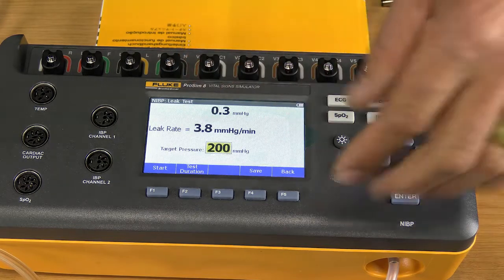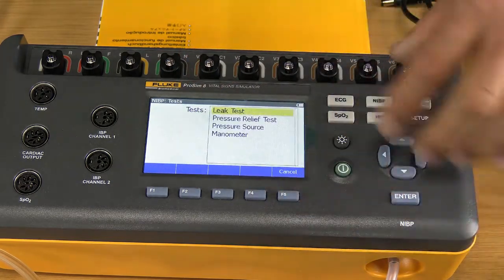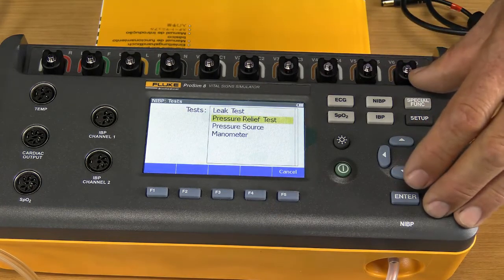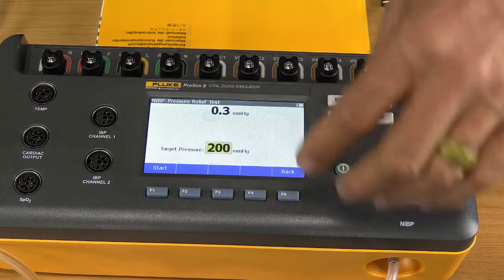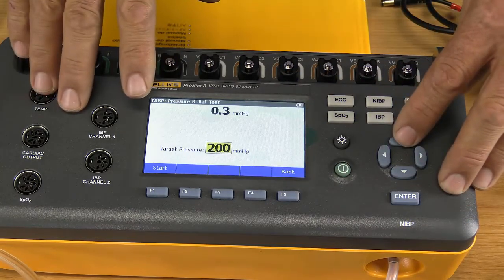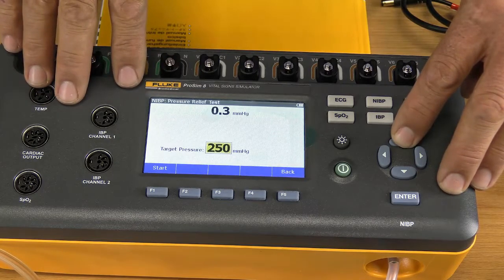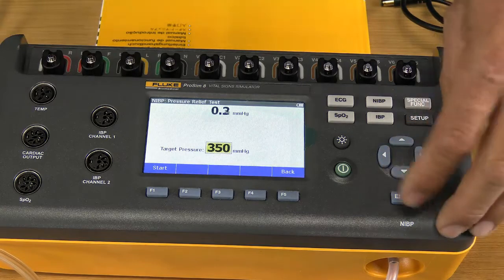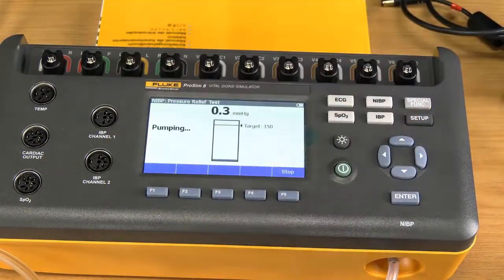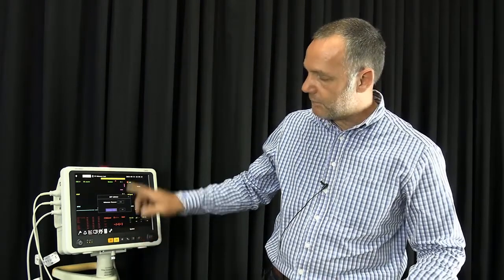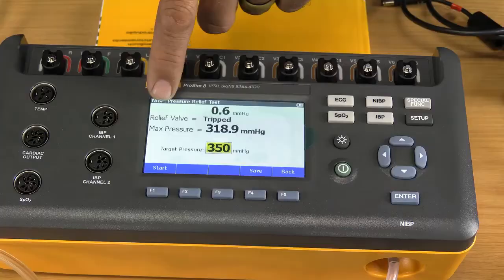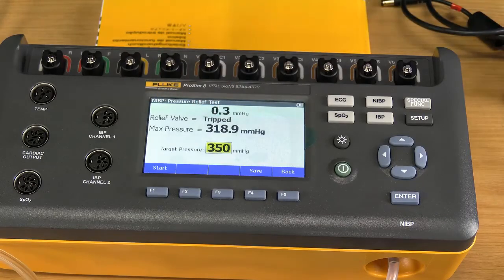Okay, then let's go back. The next test I want to do is a pressure relief test. Go there, press enter. Then your service manual will tell you what the target pressure is for your monitor. In our case, we normally set it to about 350. Say enter. I press start. The unit starts inflating, pushing my pressure up. And you can see, you heard the ping on the monitor, NIBP overpressure. And you can see my relief valve tripped at 318.9. So then you look at your service manual and see if that's within your specifications.